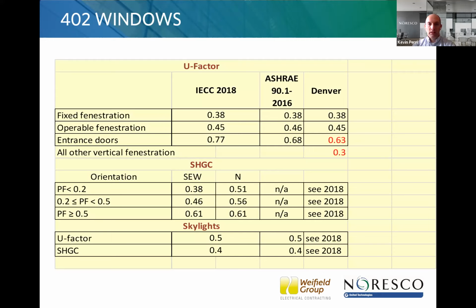So we'll get into windows. I did a side-by-side comparison here for you to show you the Denver amendments according to how they compare to IECC or ASHRAE 90.1. You can follow either one of these pathways, IECC 2018 or ASHRAE 90.1 2016, according to the Denver amendments. However, there is a slight difference you'll see in red that these two items over here, entrance doors and all other vertical fenestrations, have a different value than both ASHRAE and IECC. So just keep that in mind.